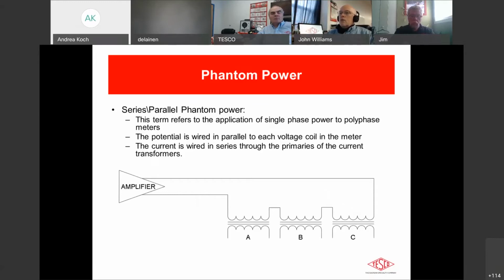Here, though, in both single phase and polyphase series parallel arrangements, you can accurately test the meter to a degree where the voltage and current are always going to be in phase with one another, and likewise for the A phase connection on the meter, B phase, and C phase. So everybody's all going up and down at the same time. And from the metering standpoint, if we look back at what Tom spoke about earlier in terms of Blondel's theorem, he spoke about it in terms of 3-watt meters. So even your polyphase meter forms are really 3 meters in some cases, at least the Blondel types are separate watt meters inside the meter. So being able to do this single phase is possible because of that independence within the meter.